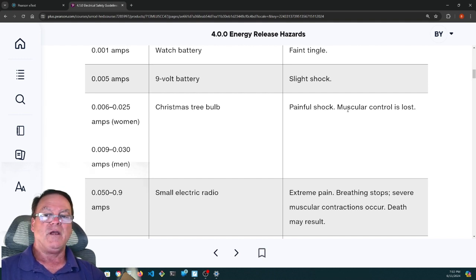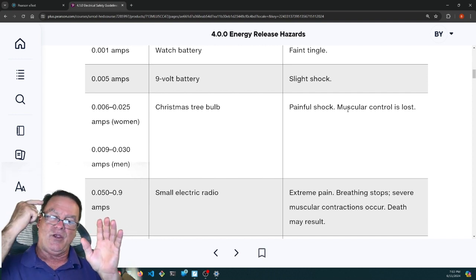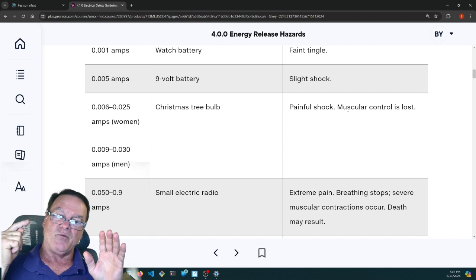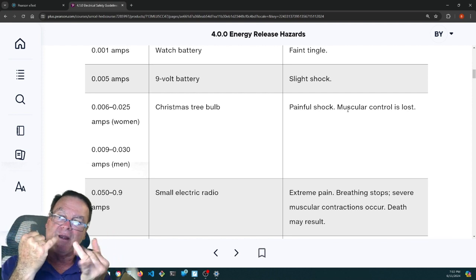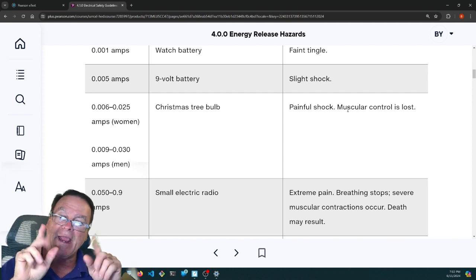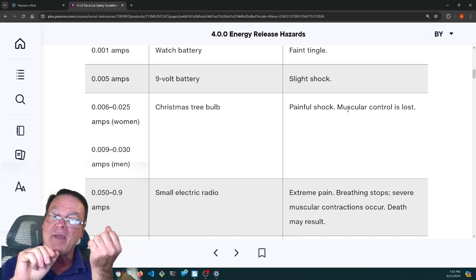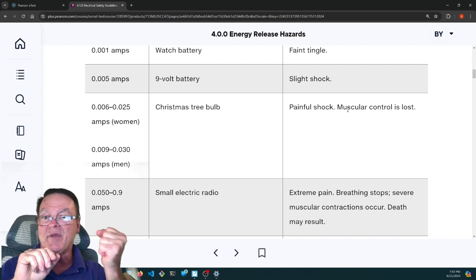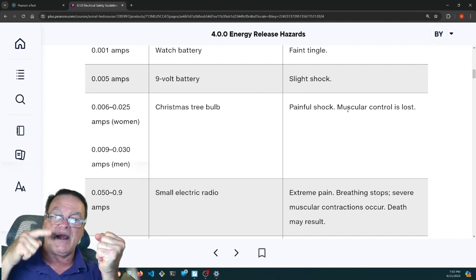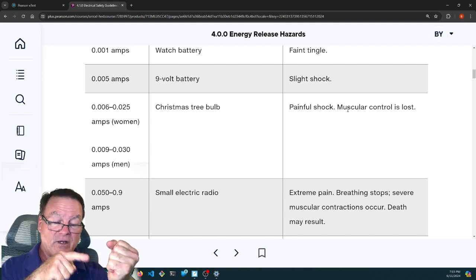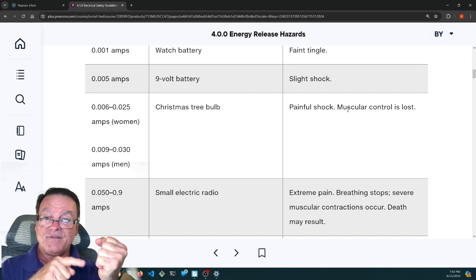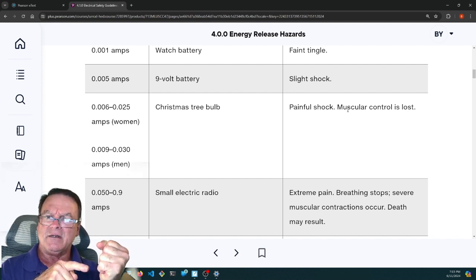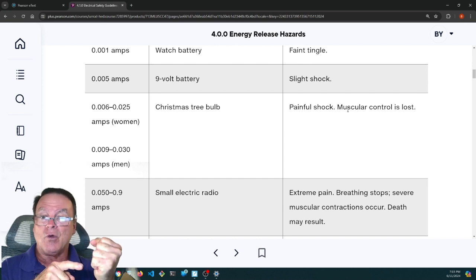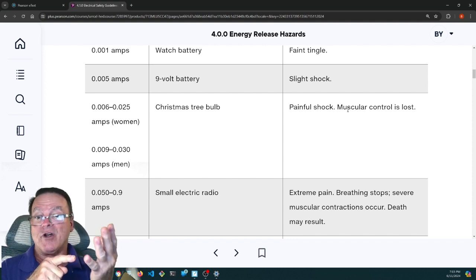Our nervous system works on electricity. We use about 8 milliamps to communicate with our bodies, letting us open and close our hands. So if you have greater than about 15 milliamps and you're gripping a hot wire, your brain is saying let go, let go, let go, but your hand is listening to the 15 milliamps telling it to hold on tight, and you can't let go. That's the let go threshold. Once you get above it, you can't open the palm of your hand.